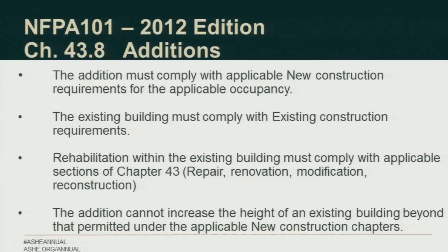And the other piece of the puzzle here is that your officer, in most jurisdictions, is going to have to deal with a building code that may have other requirements besides this. However, the question, I don't know if you heard in the back, is if I have an existing hospital that's not high-rise and I make a vertical addition that now qualifies as a high-rise, does that mean that the existing below can stay existing and the new construction above would meet new? And as an example of an issue, would the elevator foyers have to be added to the floors below? And by reading this, I would say they would not.